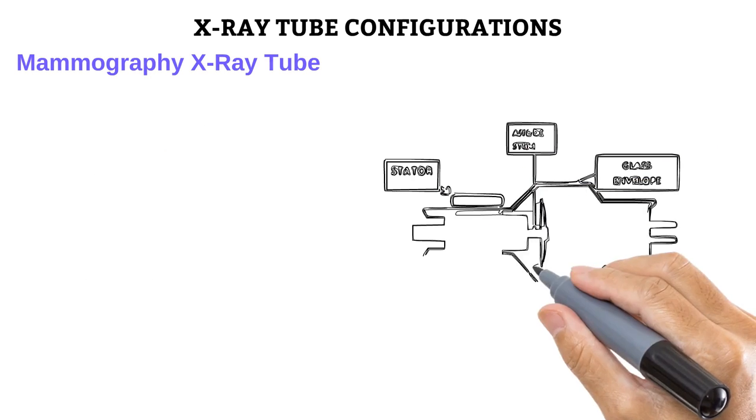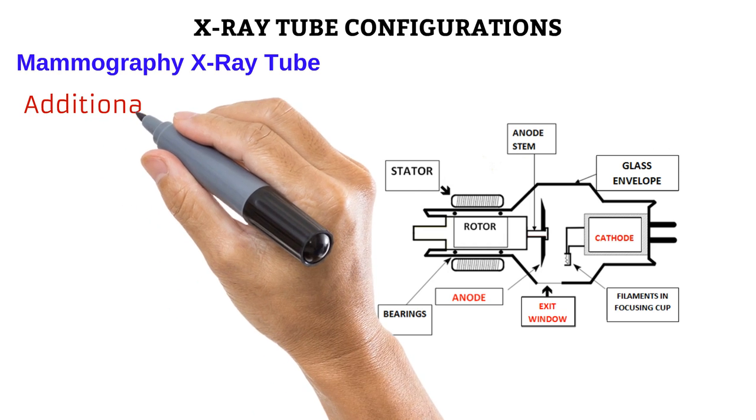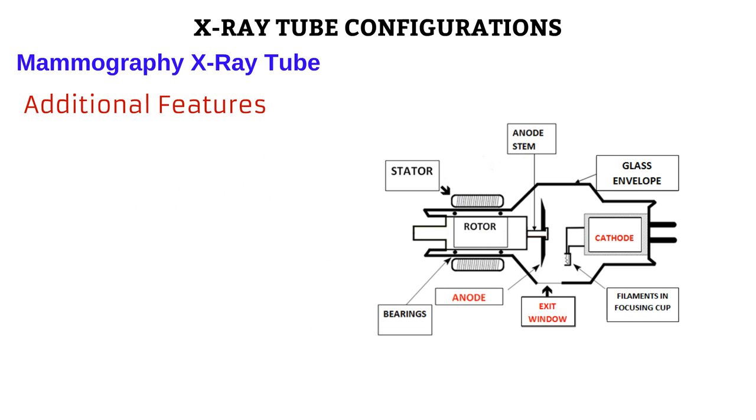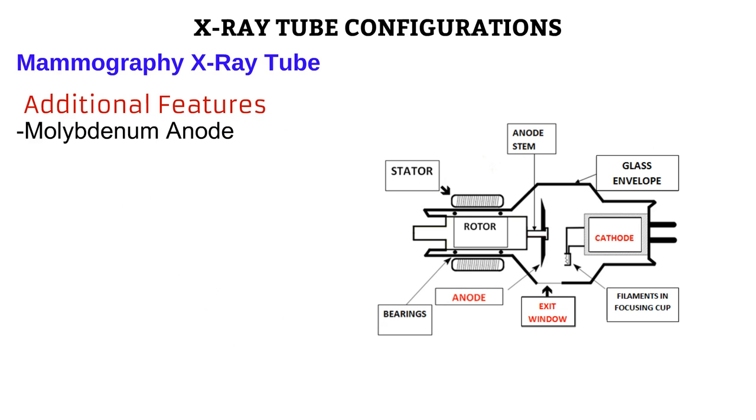Next is the mammography tube, specially designed for the mammography unit. Mammography needs a low kilovoltage due to the low subject contrast of the breast tissue. Thus, it needs a tube that can comfortably generate low-KV photons. Instead of the standard tungsten anodes, mammography tubes are made of molybdenum anodes, which offer a narrow spectrum of X-ray photons, which fall within the low-energy range needed.